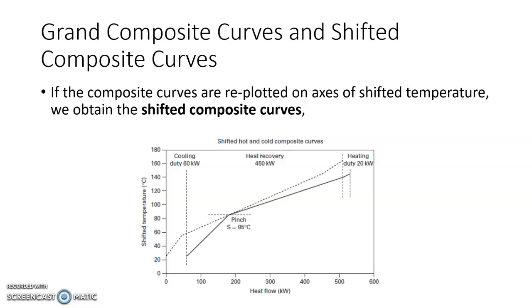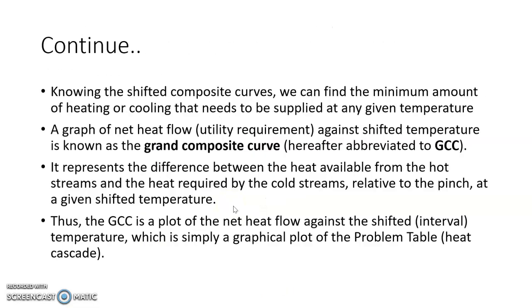Process-to-process heat recovery is 450 kilowatts. Above pinch, the hot stream falls short of supplying all the duties to the cold stream, and hence we require heating utility. Below pinch, the cold stream fails to receive all the energy supplied by the hot streams, and hence we require some amount of cooling utility. This shifted composite curve provides the same information as the actual temperature composite curve, and from it we can find the minimum amount of heating and cooling utility.